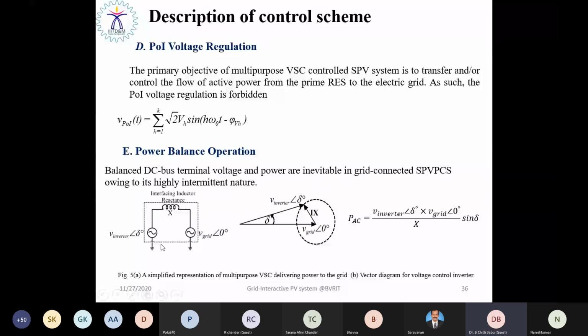So for the power balance, the inverter acts as a sending unit, as we are transferring power from the inverter to the utility grid via the interfacing inductor, right? So it can be modeled as a power system that has a sending end and receiving end. We transfer the power through line reactance, right? So this is the power expression while you are transferring power from the inverter to the grid, and it has a phase angle difference of delta and 0, so that power can be transferred from inverter to the utility grid, and that it is inversely proportional to the line reactance, so that has to be designed with a very low value.